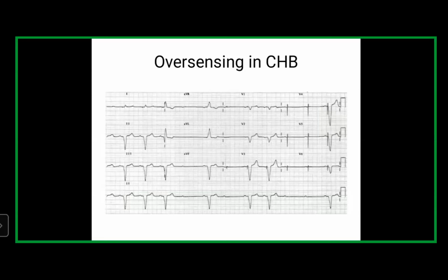The device in this case should have paced following the atrial depolarization, but perhaps there is some oversensing. I'm not sure. I can't really pinpoint which direction, but this shows some level of oversensing because it's not pacing.